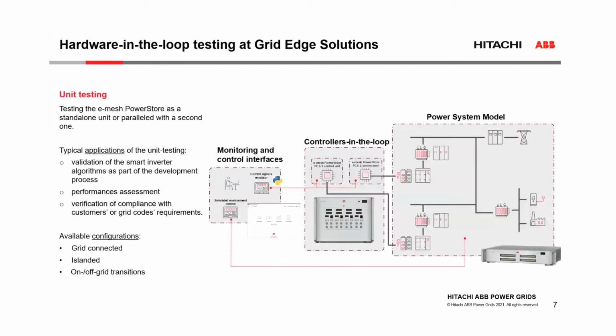Unit testing is our simplest application of hardware-in-the-loop technology. We use this method very extensively to validate our e-mesh PowerStore. As I said earlier, the e-mesh PowerStore is our battery energy storage solution, and it is required to operate in both grid-tied configuration and off-grid. Therefore, we need to test it in both conditions, and also make sure that transitions between these conditions can be done optimally.